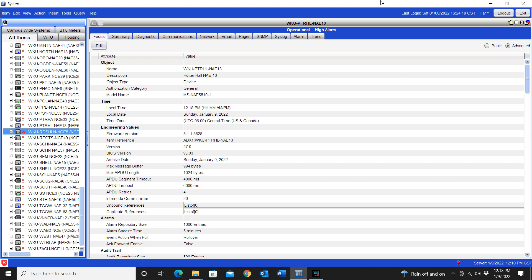If you do have remote access to your server or if you have any kind of direct access to your server and are able to browse into the device, then there is something that may be a little more of a challenge to overcome. There is a file within your server that we need to take a look at. If you can browse to your device from your server, it is obvious that your server is able to communicate with it, but then there is something going on within Metasys itself. And again guys, this is just a guide, a help. This may or may not be your particular issue, but I wanted to share some of this information with you all just in case that it is.